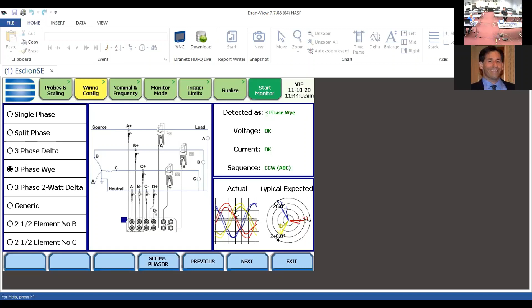The other thing you have is a reference point. If I'm connected to a delta circuit but my application is a Y circuit, how do I connect to that circuit? Rather than leafing through a user's guide, the diagram is right here and easy to follow. You also have your phasor display, which tells you how you're actually connected and what the typical connection should be based on the circuit type. That's what I call a sanity check. Also, if people prefer real-time waveforms, you can use them via scope mode.